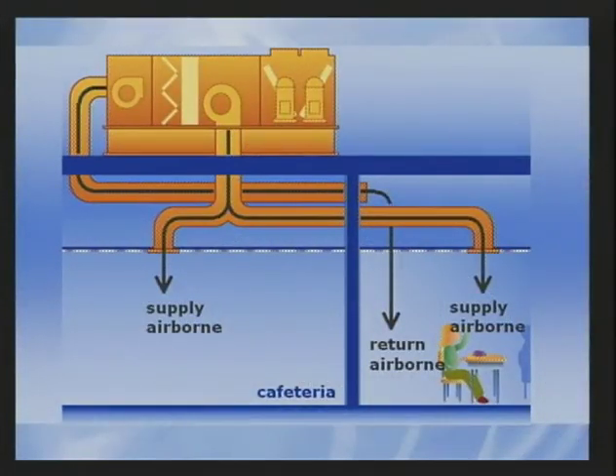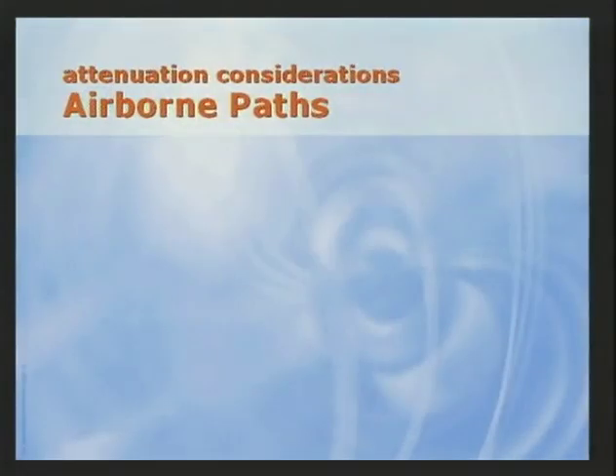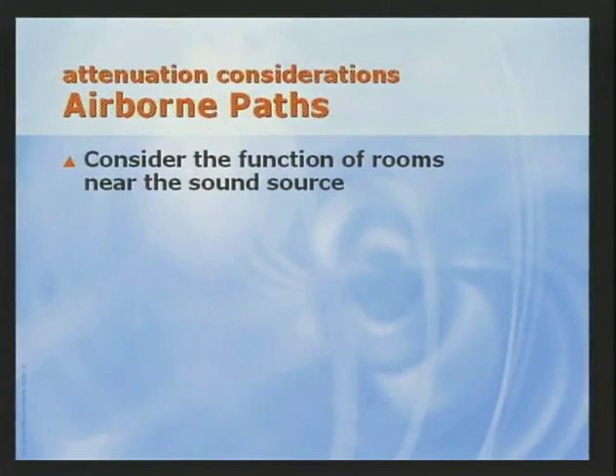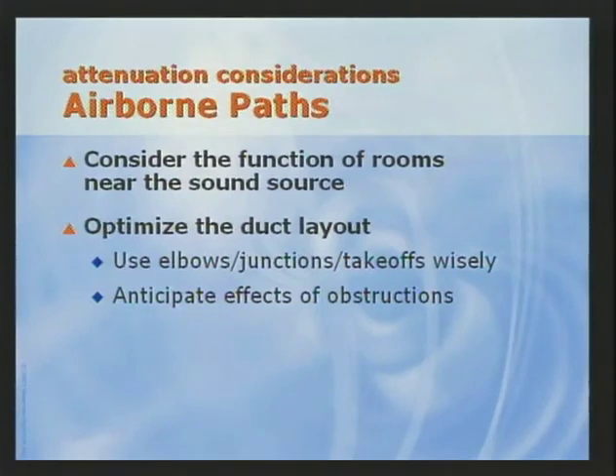Airborne paths for central systems are similar to the airborne paths of near room units. The main difference is that many of the rooms served by the central unit can be a considerable distance from the sound source. Lining the ducts, or even just the first few sections of ductwork, is typically all that's required to sufficiently reduce the in-duct sound levels. Of course, there are some exceptions. First of all, pay particular attention to the rooms closest to the sound source. These rooms do not have the distance advantage. Secondly, poorly designed ductwork can generate sound. The effect of elbows, junctions, and takeoffs can be calculated, but watch out for those surprises that show up when ductwork is wrapped around a pipe, beam, or other obstruction.